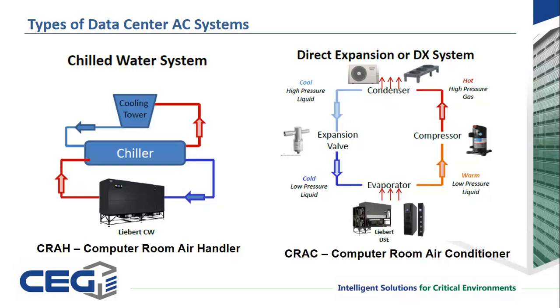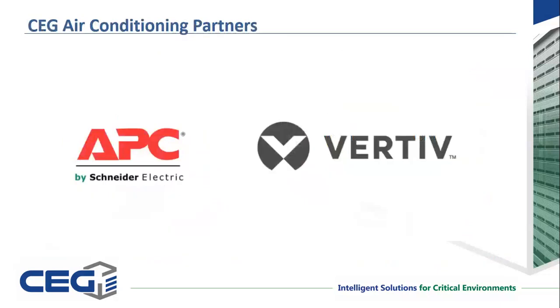There are some hybrid systems out there, and some really unique things manufacturers are trying to do with cooling efficiency. Emerson has a product called DSE that is a hybrid between the two. There's also a concept called free cooling or economization where you're taking advantage of seasonalities and cold air in the wintertime. Both chilled water and DX systems kind of look the same when they're sitting on the raised floor or on a slab floor — it doesn't matter until you start asking questions or look under the floor at chilled water lines versus refrigerant lines.